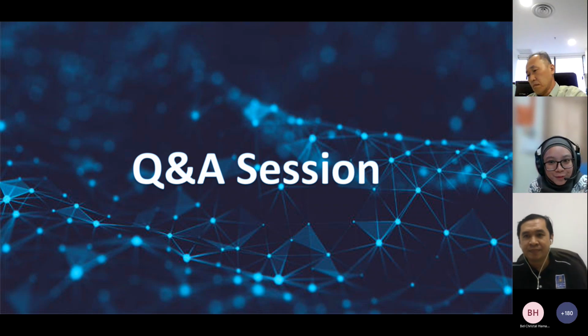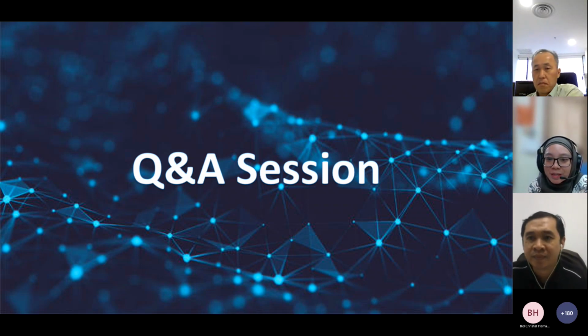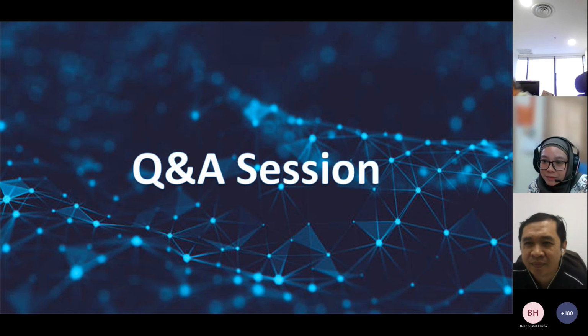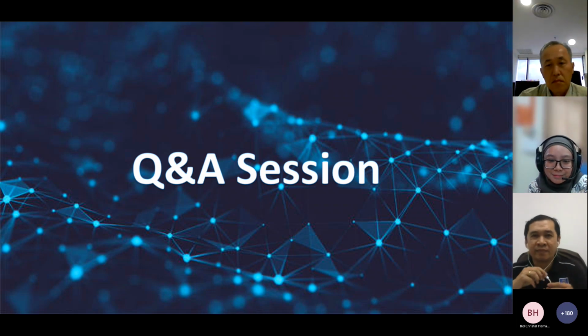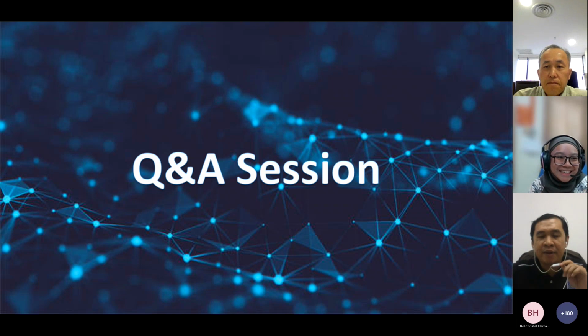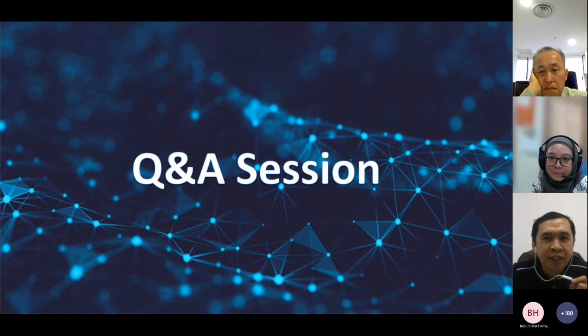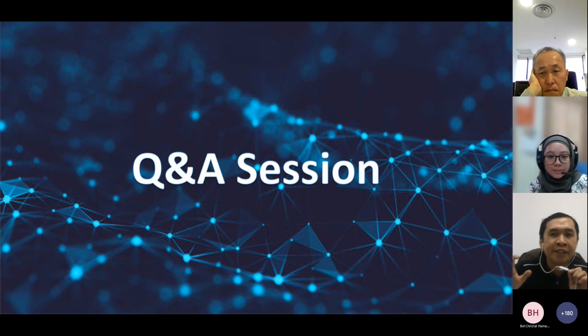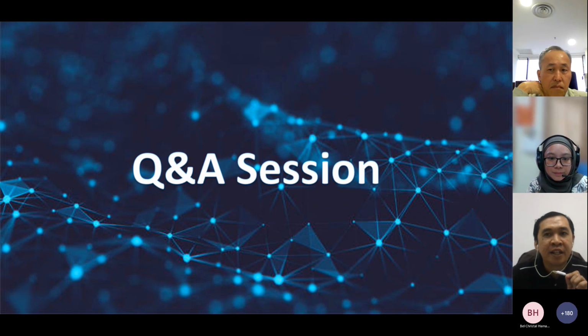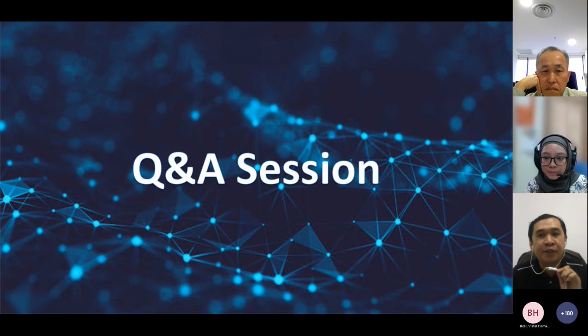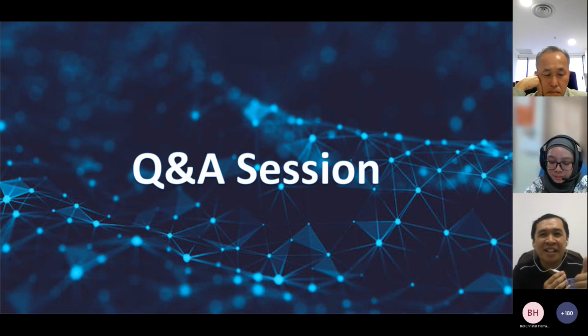We have another one also from Goh Kian Hui. How to ensure the calibration equipment test sets themselves are good to be used prior to performing calibration on the client's equipment? Okay, thank you very much. This is referring to the standard equipment that is used for calibration. If you want to know whether the test set is good or not, that's why we need the calibration. As I mentioned just now, number one, you need to identify your measurement uncertainty.